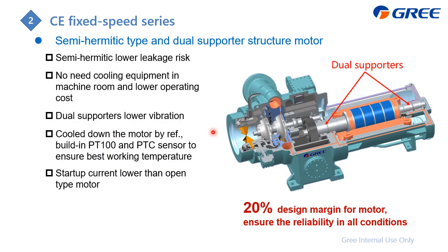This is the sectional view of the CE on-off compressor, and from here you can find the motor, and there are two supporters, which are the bearings, and this is the speed up gear, and also there are two stages, which means two impellers for compression. And here is the suction side. Then after compression, the refrigerant will flow out from here, this hose. And also you can find it is semi-hermetic, which can lower the leakage risk. And also there is no need for a cool down machine or equipment, because we use the refrigerant to cool down this motor. This can lower the operating cost.